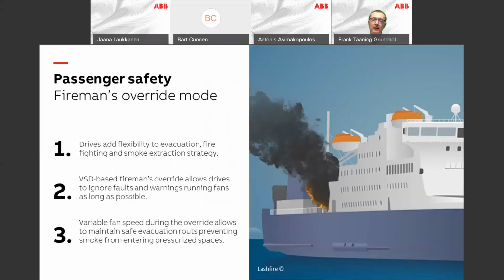When we talk about combined use, or even dual installations where you have one fan for ventilation and one for smoke extract, the important part is that when there is a fire situation, we have to make sure the units run as long as there are passengers in harm's way, or as long as the fire brigade needs access, or the crew needs access to an area. Because we need to remove the smoke out of the affected areas - it's the smoke that kills. So ventilation is crucial for managing emergencies when it comes to fire situations.